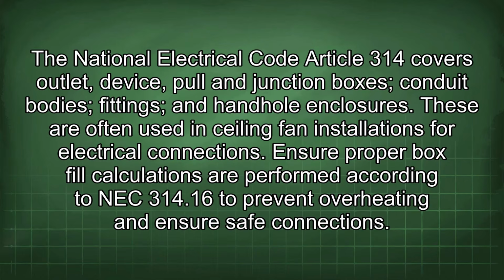The National Electrical Code Article 314 covers outlet, device, pull and junction boxes, conduit bodies, fittings, and handhole enclosures. These are often used in ceiling fan installations for electrical connections. Ensure proper box fill calculations are performed according to NEC 314.16 to prevent overheating and ensure safe connections.